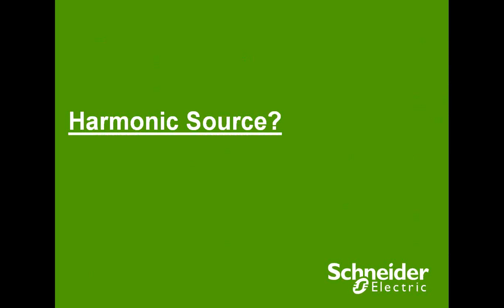Let's look at where harmonics are coming from. There are 3 types of harmonic source. The load gives harmonic current to the system, like non-linear loads. Then we have voltage converters, that's transformers: when you operate a transformer beyond the saturation point, harmonics come into the picture. Then alternators or generators: if the winding pitch is less than the pole pitch, you will definitely get harmonics from the alternator as well. But our main concern is the harmonics from the load side, because we cannot solve the harmonics coming from a generator or transformer unless we design the machine perfectly. So today's discussion will only be on the harmonics coming from the load side.